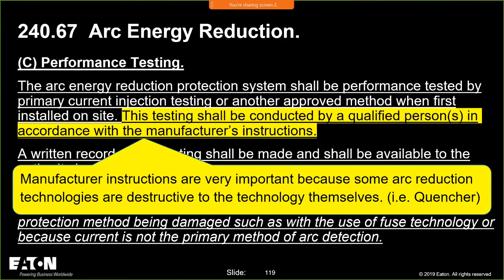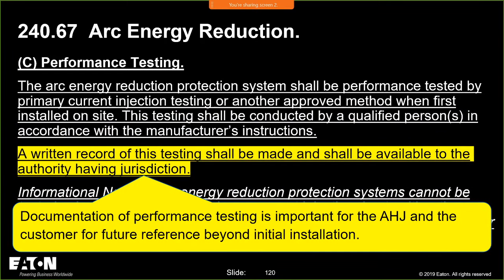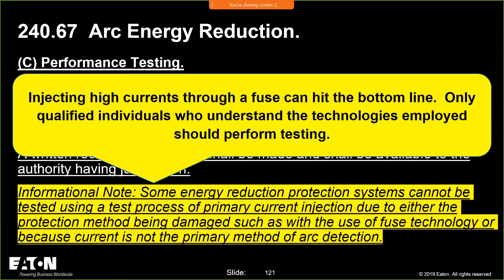You're going to make sure that whoever's doing it is qualified. And I would say that if you're out there doing primary current injection testing on your GFPE, you're going to want to get this done at the same time. Don't let him go out and do 230.95 testing, go home, and then have the inspector tell you, you need to get them back out there to do this testing. You need to have a written record. And again, some energy reduction methods can't be tested because it would damage the equipment. So like a fuse, if I try to show you and prove to you that I'm going to actuate in 0.07 seconds, I'm going to open that fuse. You don't want to do that.